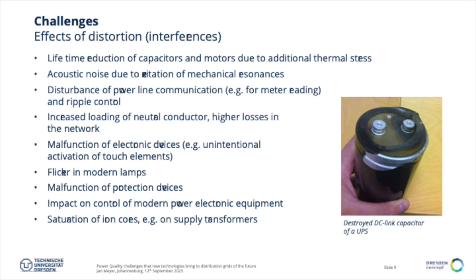You can have disturbances of power line communication, which in some countries in Europe is heavily used for meter reading, the smart meter concept. The communication is in the CENELEC band A, between 3 and 95 kilohertz, and this can be seriously disturbed.